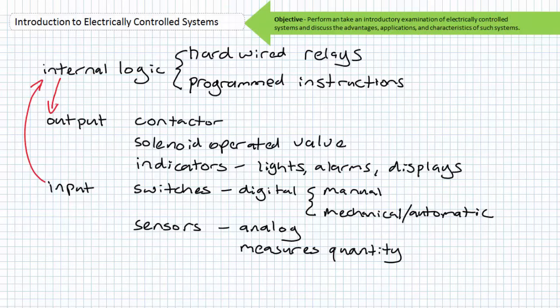Regardless, the instructions written inside a PLC program are programmed in the exact same manner as one would employ a relay inside an electrically controlled system employing traditional hardwired relay-based ladder logic. The fundamental difference between these two types of systems can be summed up as this. The control relays inside a system employing traditional hardwired relay-based ladder logic are real. The instruction set inside a system employing a PLC mimics the function of control relays.